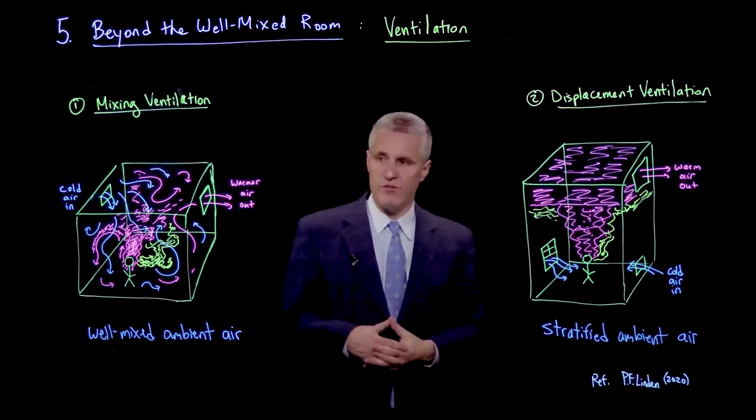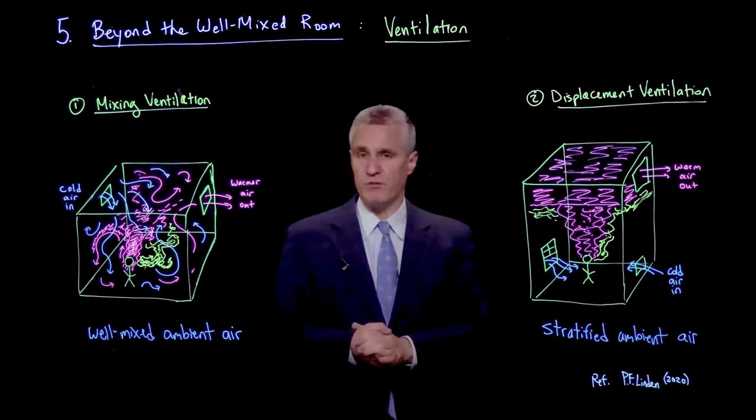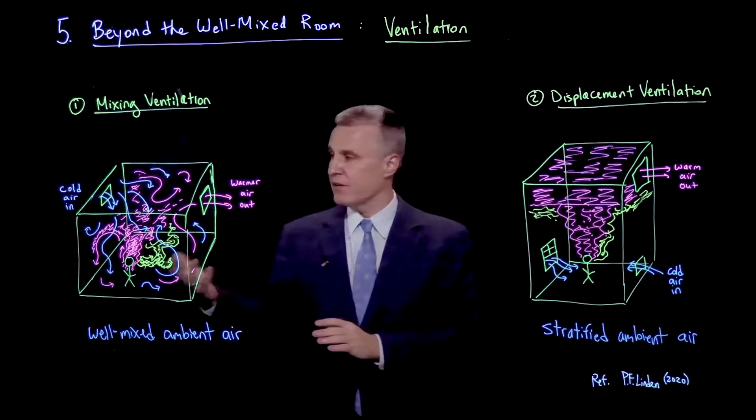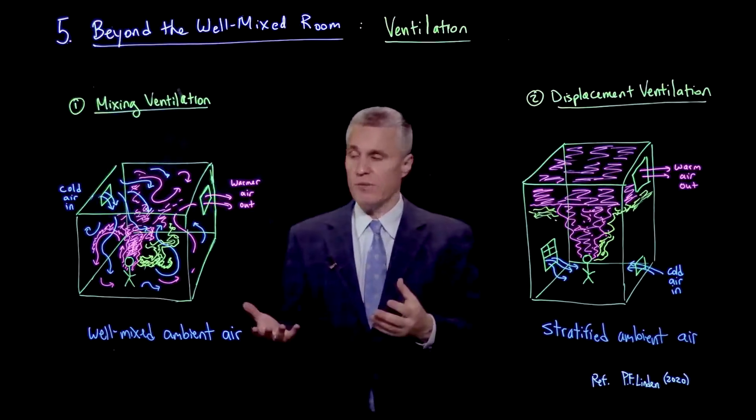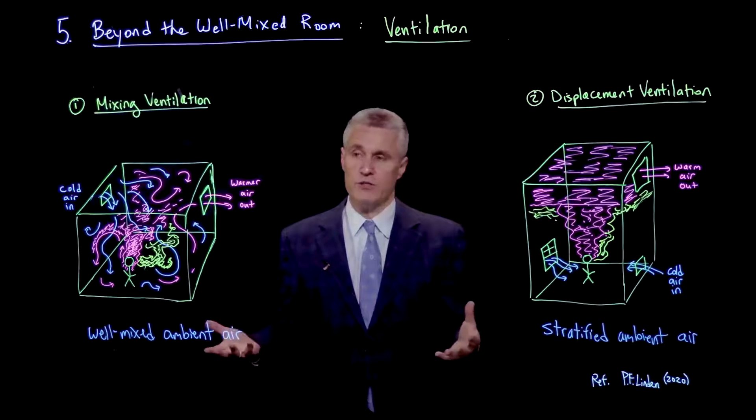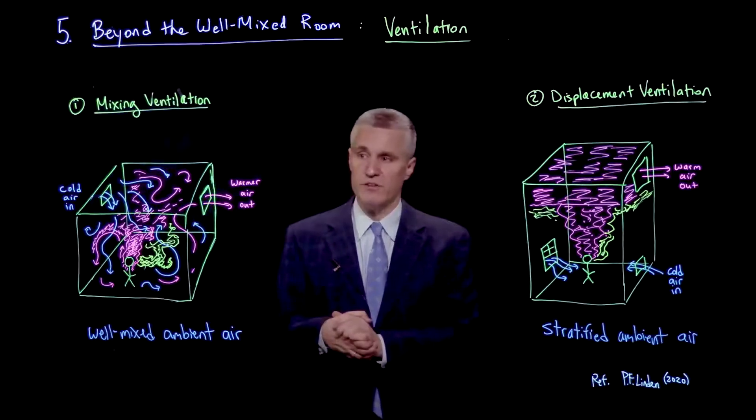So that can actually be a situation where a less well-mixed room can be better. On the other hand, the advantage of a well-mixed room is that the pathogen in the droplets is diluted throughout a larger space, and that can be more advantageous.